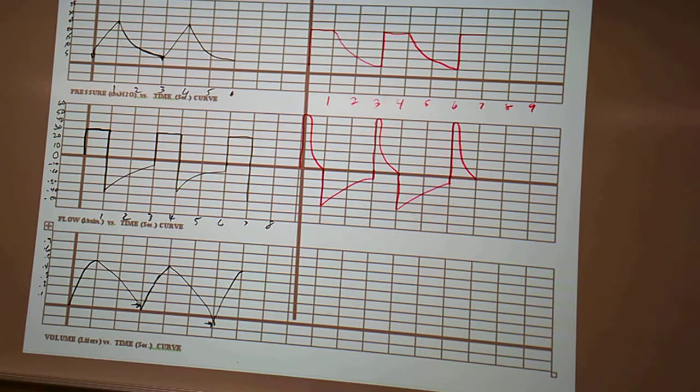Once those airways are pressurized to my target pressure, the flow starts to decelerate until, at the end of the breath, all the lungs are full. So what you're filling are basically small airways, which are very laminar, towards the end of a pressure controlled breath.